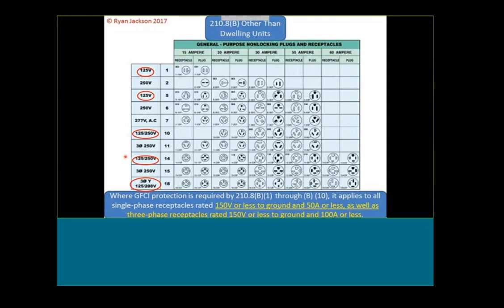Let me go down to column 14 where it says 125/250, and move over to the 30 amp column. You might recognize that as a dryer receptacle, a 30 amp, 250 volt rated receptacle. It's actually rated 125/250, which means 150 volts or less to ground, 50 amps or less.